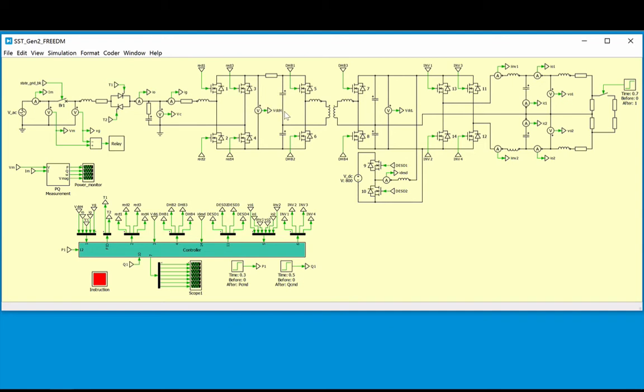A second stage, known as a dual half-bridge, then uses a conventional, but high-frequency transformer, to step down the power to a 400 volt DC link on the secondary side. The third stage includes an inverter, operating at 40 kHz, which generates 120 volt AC power for consumption in homes and businesses, for example.